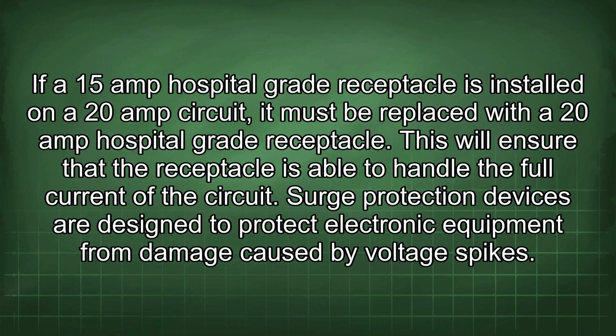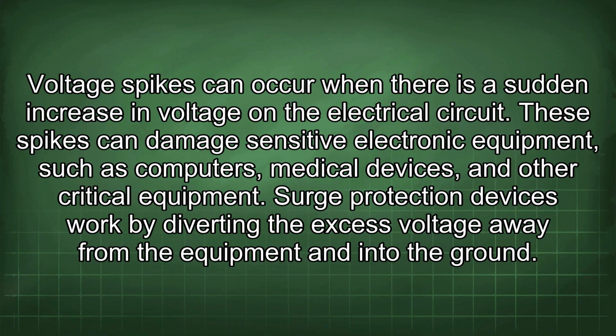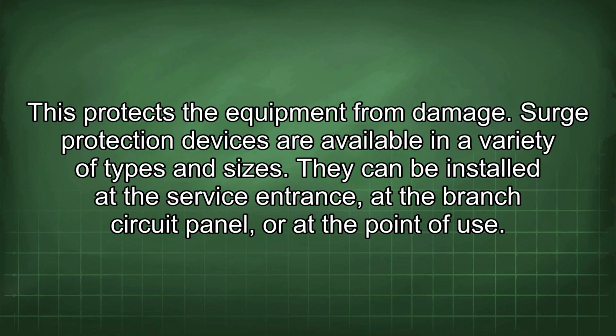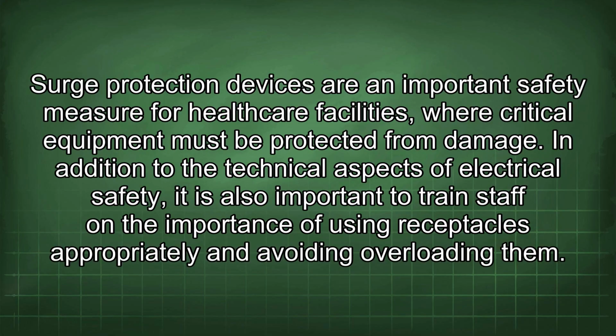Surge protection devices are designed to protect electronic equipment from damage caused by voltage spikes. Voltage spikes can occur when there is a sudden increase in voltage in the electrical circuit. These spikes can damage sensitive electronic equipment such as computers, medical devices, and other critical equipment. Surge protection devices work by diverting the excess voltage away from the equipment and into the ground. This protects the equipment from damage. Surge protection devices are available in a variety of types and sizes. They can be installed at the service entrance, at the branch circuit panel, or at the point of use. Surge protection devices are an important safety measure for healthcare facilities where critical equipment must be protected from damage.